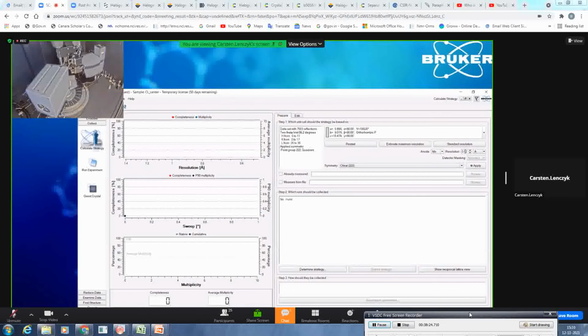And you see here, it already suggests a resolution it could collect. For that, we would go to a reasonable one. Basically, for molybdenum, I always suggest 0.75. With the fast scan, you most of the time have the ability to already make a pre-structure solution, so you will also get a hint about the space group most of the time.